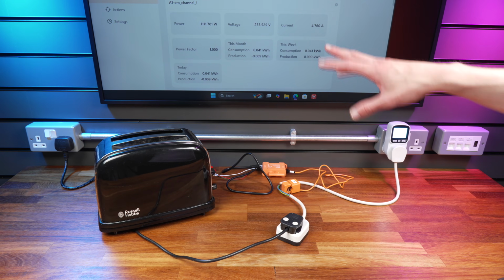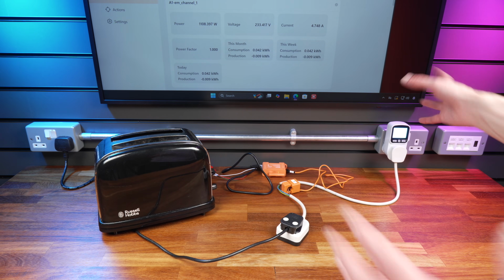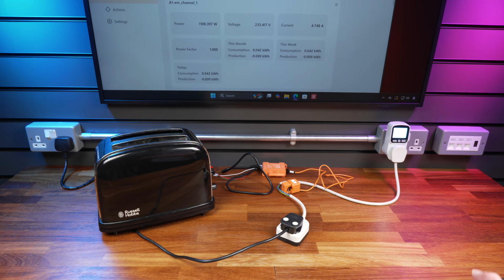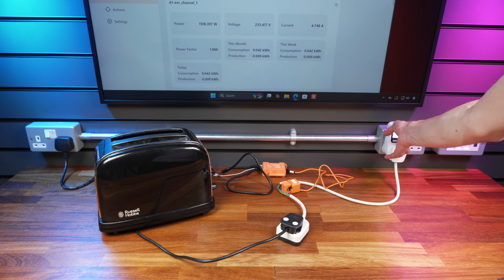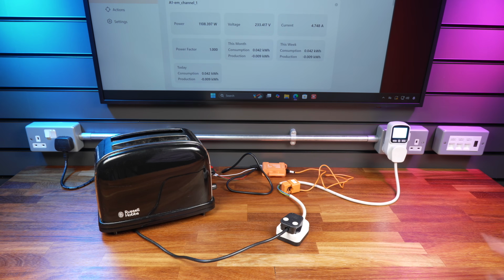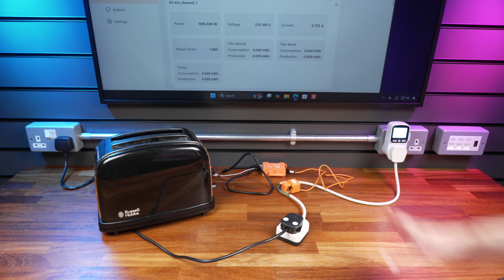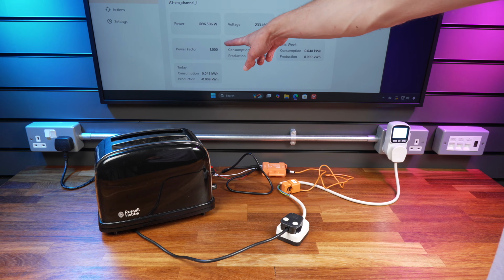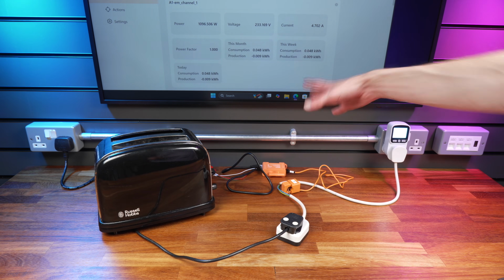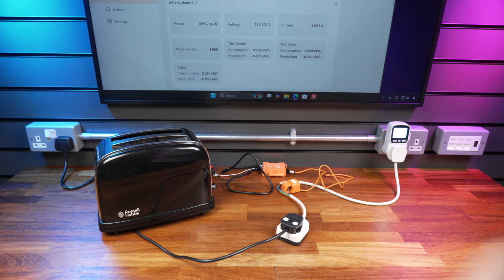Of course it'll jump around a little bit, we're reading them at sort of instantaneous times on two separate devices, so we'll be reading them at slightly different points in time. But then 4.74 amps or so. Down here we're reading 4.79 amps, again that's different times again, so yep, all seems pretty accurate. And obviously with this being a purely resistive load, we have a power factor of 1, meaning that if we multiply the voltage by the current, we will get the exact same value as we have in watts.